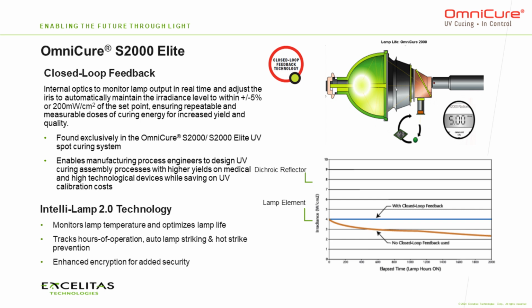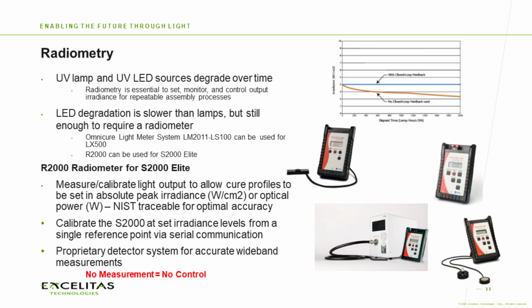So you can assure that you're always in control with the S2000 Elite, which gives you the benefit of higher yields because you have a more reliable process, and you can also save on calibration costs because although it is advisable to calibrate the system, closed-loop feedback keeps you in control until the next calibration cycle. In terms of IntelliLamp 2.0 technology, this is really a technology that tracks the hours of operation, displays those for you in the UI, and also prevents a hot strike condition from happening. So it extends the life of the lamp.